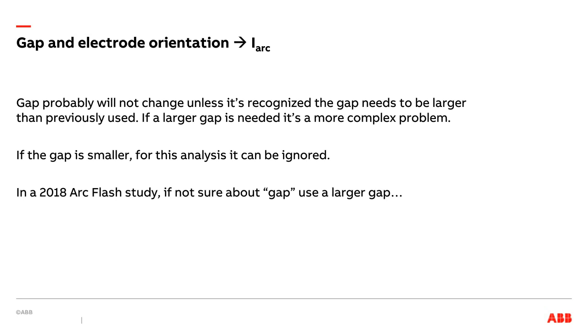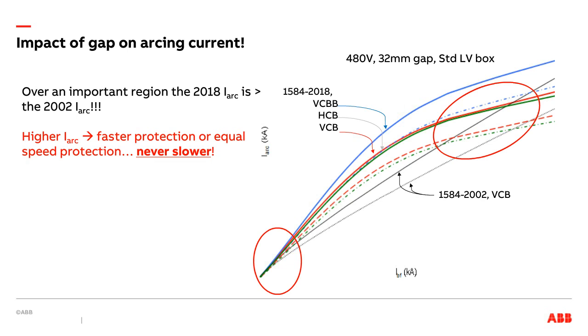If you are doing an arc flash study, a little side point, and you're not sure about the gap, use a larger number. Using a larger number always is the conservative thing to do. Again, we can discuss that in detail at a different time. Let's look at arcing current difference between the old study and a new study for similar conditions.